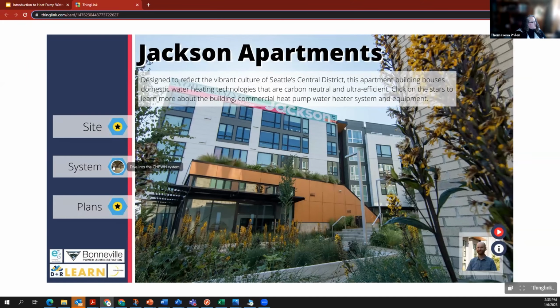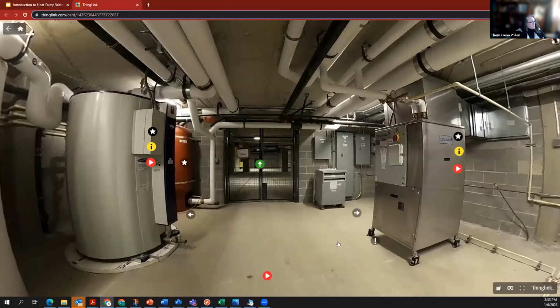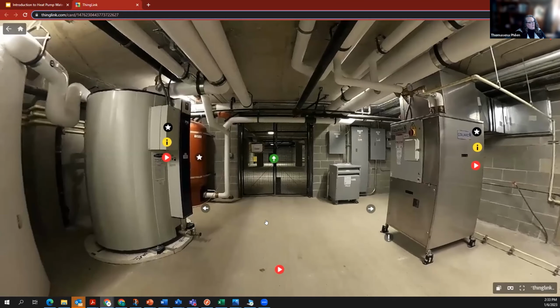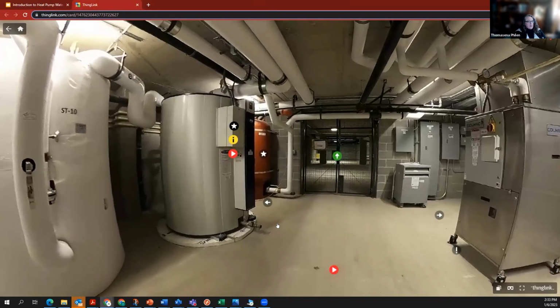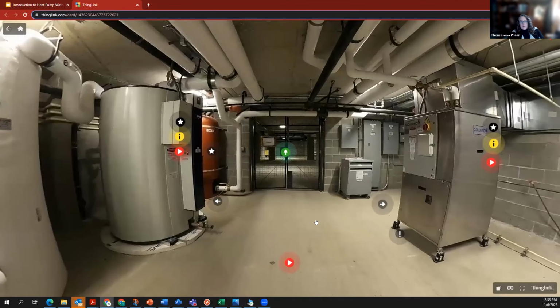at the system itself. And this will take us to the parking garage of the Jackson Apartments. Like I said before, there are 156 dwelling units in this apartment complex. This room takes up 4 parking spaces in the underground parking garage. And so the question comes up sometimes, so why do you have it in a parking garage? And the primary reason is air buffering. It does get kind of cold up in there. And these units here, this particular brand, is not designed to go in the outside. It doesn't need to be indoors with you, but it does need to be sheltered. And the air does need to be buffered somewhat because it's a 134A system, and it will not continue to heat water below about 32 degrees. And so this particular type of unit is in the parking garage.